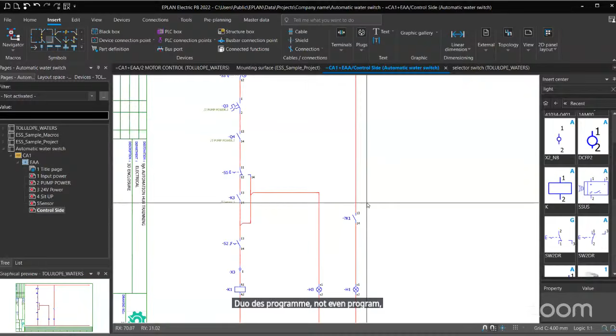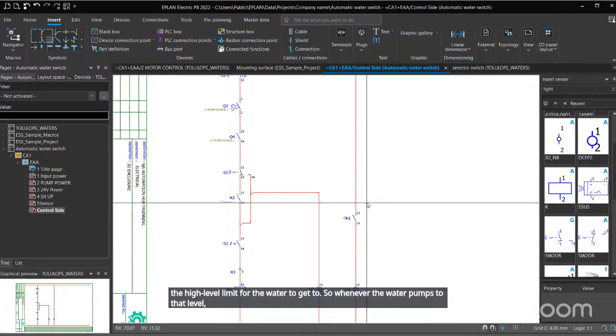Because you would have programmed the depth that will be triggered, that will trigger the relay, right? Yes, on your ultrasonic sensor, every sensor has tuning, so you can increase or reduce the sensing range. That is during the process of fine-tuning, not even programming, just fine-tuning. There must be a place where you can increase or reduce the sensing range, so you reduce it to where you want the high level limit for the water to get to. Whenever the water pumps to that level, it sends 24 volts out, the power cuts off, this happens, so we are good to go.